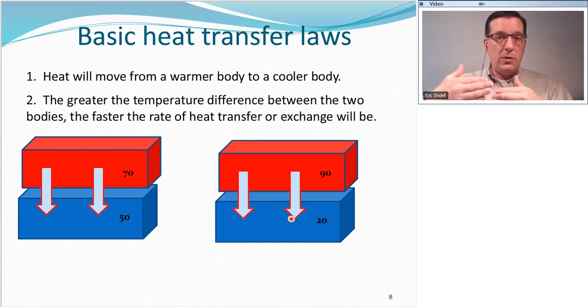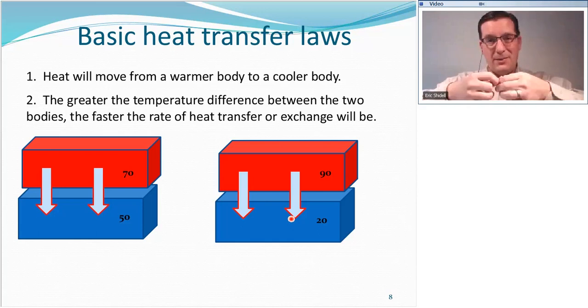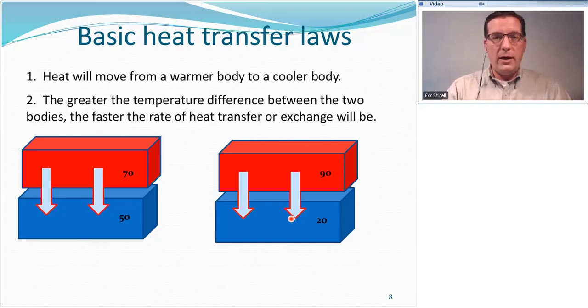The faster the heat moves from inside to outside, the faster our heating system has to replace that heat as it's being lost. So you can almost think of your home or your building like a bucket with a hole in it. And the size of the hole gets bigger the colder it is outside, which means that the faucet putting the water back in, that's our heating system, has to add heat at least as fast as it's draining out the bottom of the bucket. So in that way, you can kind of imagine heat being a quantity of a substance moving over time. And it's always going to have that time frame. And as we move forward into talking about emitters, this temperature difference idea is always going to be important.